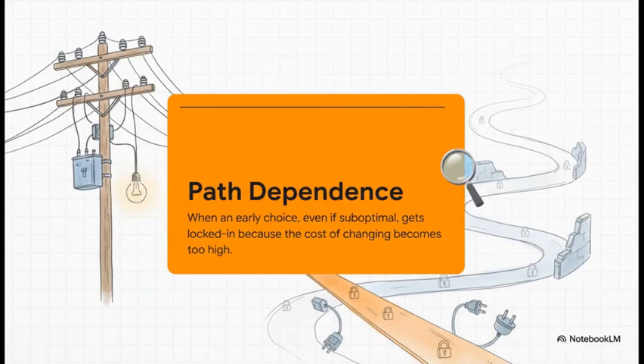But that choice confirms the system's limitation. To accommodate the legacy 120-volt need, we are forcing commercial and large residential spaces to accept mathematically inferior power delivery, 240-volt appliances running at 75% power. That is a measurable cost in performance and time, and it stems directly from the foundational decision to lock the neutral to a 120-volt potential. I stand by the fact that the 208-volt anomaly is an edge case of industrial reality.